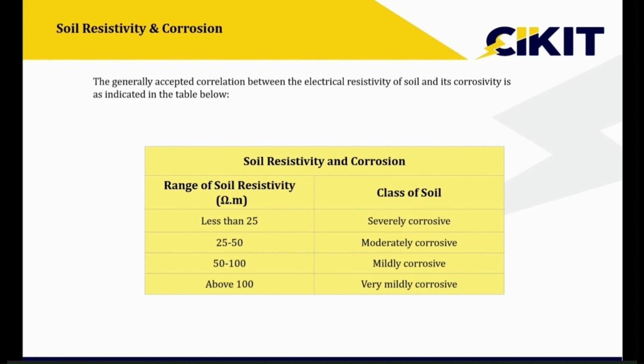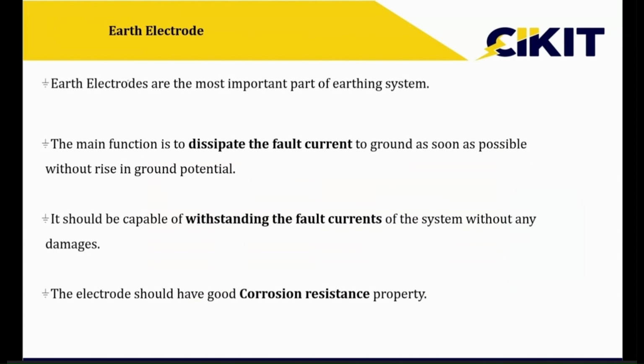So if I have a soil site condition with very low resistivity, say 10 ohm meter for example, in this case I can easily achieve a lower earth resistance value, but the problem is the lifetime of the earth electrodes will be much lesser because the soil is severely corrosive in nature. So the lifetime of the earth electrodes you are using depends upon the type of soil in that particular locality. Right. So the first component is earth electrodes.